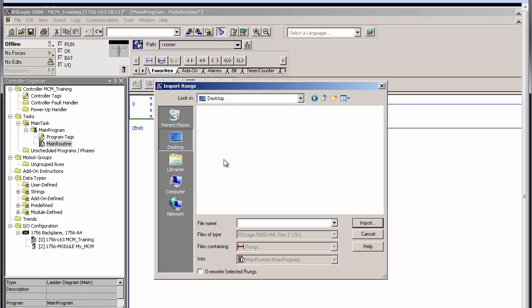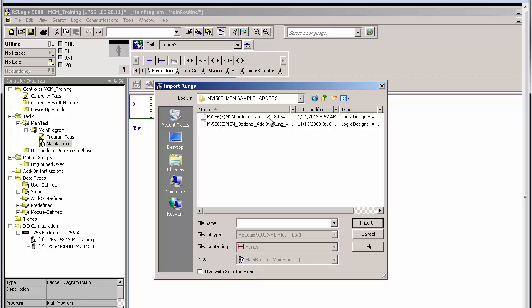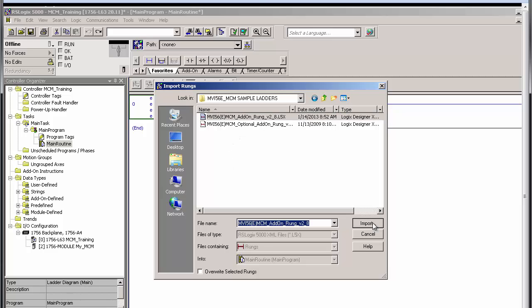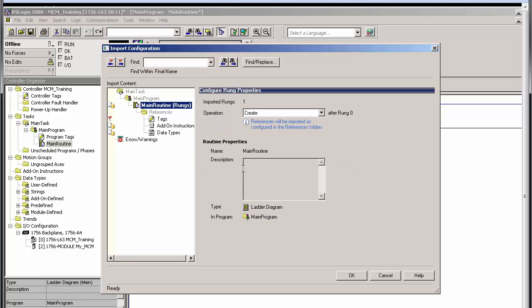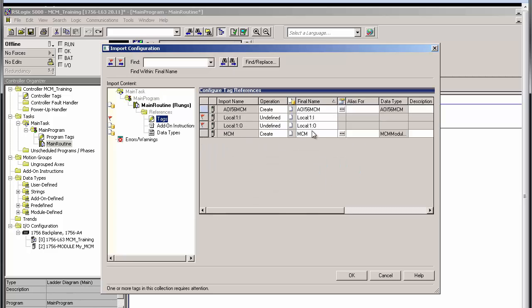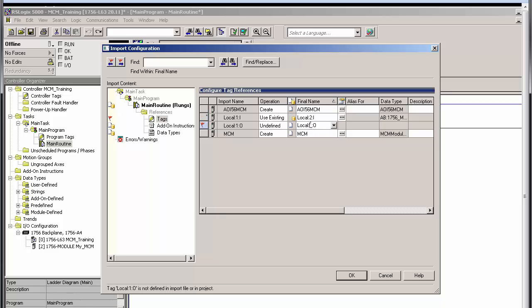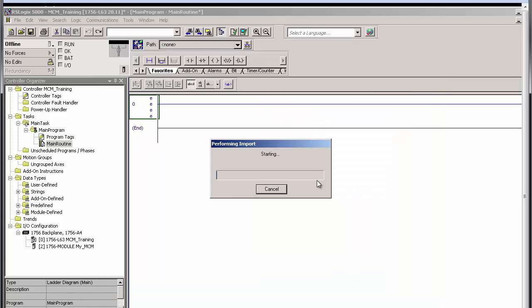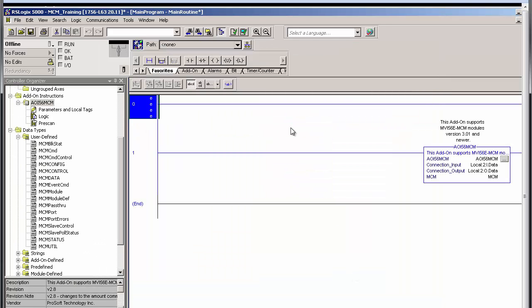When the Import Configuration window opens, change the slot number by modifying the local slot number field to match the number of the slot that the MVI56E MCM is actually using. In this case, I have the module in slot 2 of my rack, so I'll change each field to slot 2. Once this is done, click OK. Return to Main Routine and delete the empty rung 0.